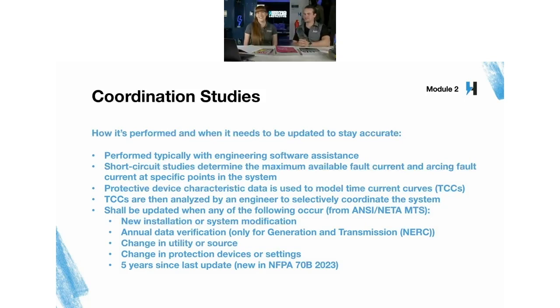diagrams. And then typically those are analyzed by an engineer to selectively coordinate the system. Basically looking at it and making sure that they're in the right order for the fault current scenarios that you're evaluating. And we'll show you what we mean in just a couple more slides. We have an example of one that was not coordinated well, and then after some analysis, what the curves would look like if it was coordinated well. Right.